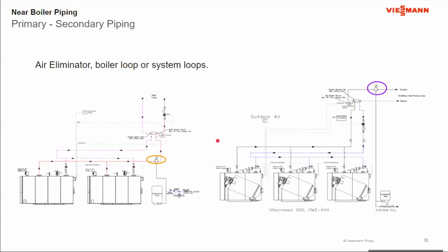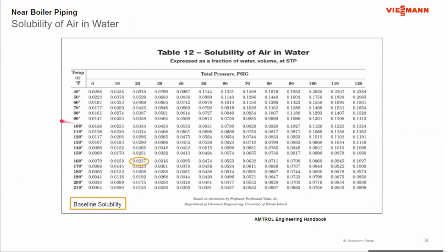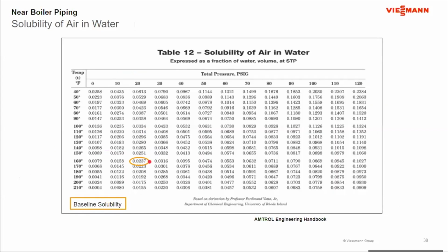And it really all comes down to solubility. So here's the solubility table. I pulled this out of Amtrol's Engineering Handbook, something I recommend that everybody has available. If you don't have a copy of it, if you go to, I think, heatinghelp.com, I think they've got that in their library. But this table shows the solubility of air in water, and solubility is really tied to 2 things, pressure and temperature, okay? And right here, I'm going to call this baseline solubility. And that baseline solubility, I'm going to call it right here, okay? So baseline solubility is going to be based on the pressure at that point, and then if I look at the temperature that's coming out of the boiler.